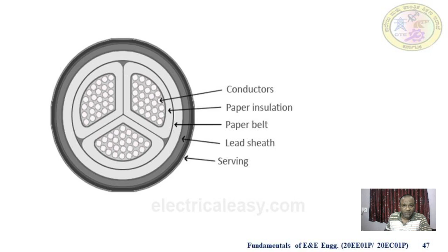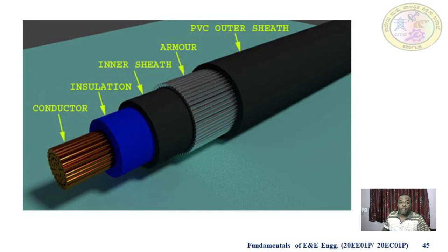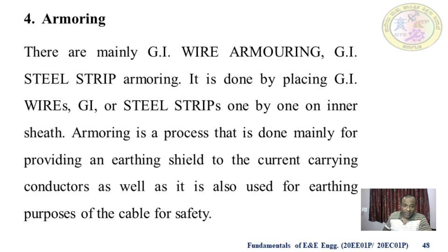Next is armoring. There are mainly GI wire armoring and GI steel strip armoring. It is done by placing GI wires or steel strips one by one on an inner sheath, as you see in the figure. Armoring is a process that is done mainly for providing an earthing shield to current carrying conductors, as well as being used for earthing purposes of the cable for safety.